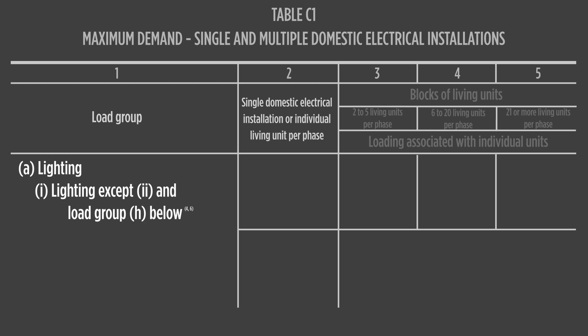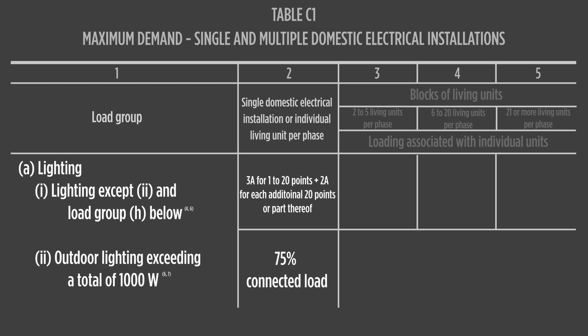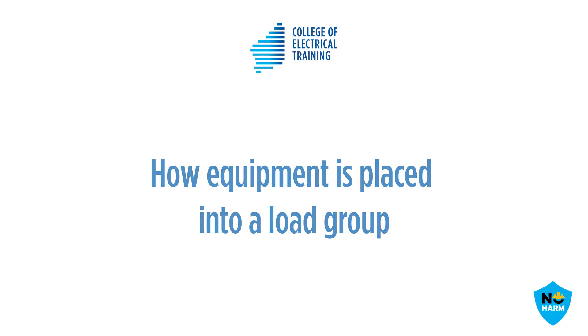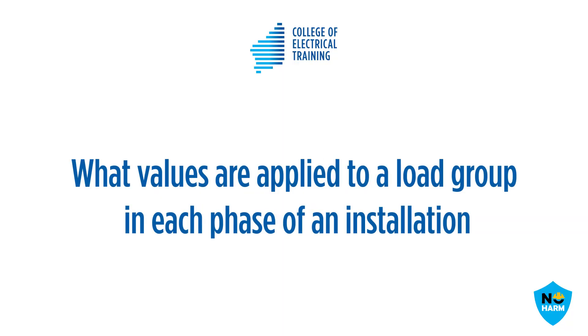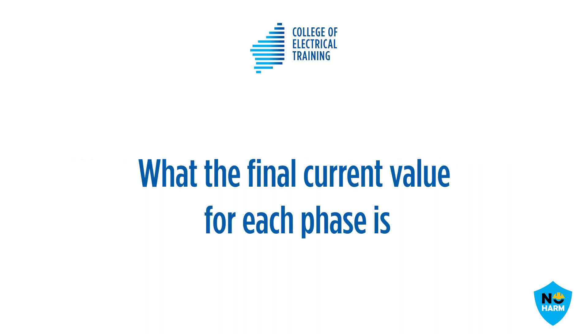Any load will contribute something to maximum demand calculation, so all loads must be allocated to a group. ASNZS 3000 has worked maximum demand examples in Appendix C for guidance in the calculation process. These examples show how equipment is placed into a load group, what values are applied to a load group in each phase of an installation, and what the final current value for each phase is.